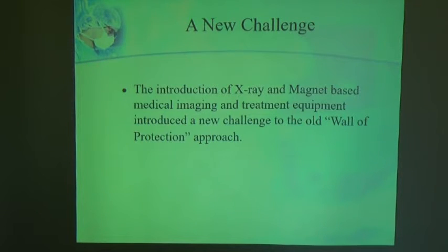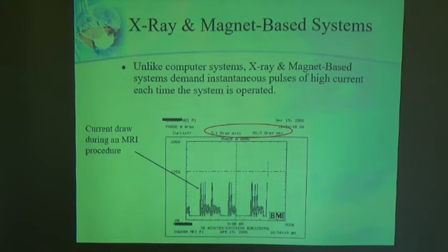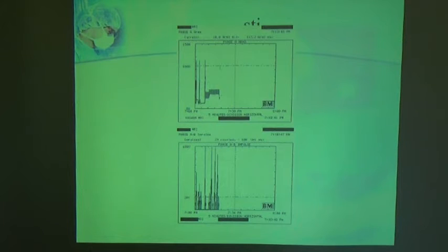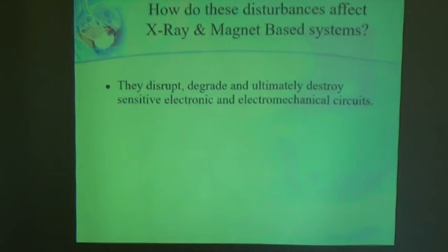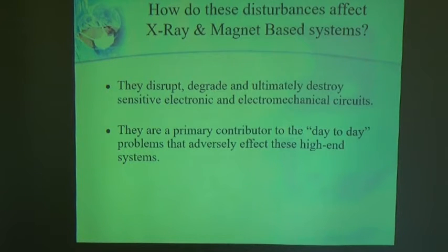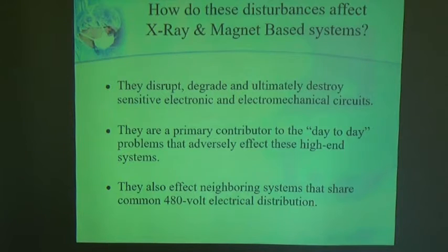The introduction of X-ray and magnet-based medical imaging and treatment equipment introduced a new challenge to the old wall of protection approach. Unlike computer systems, X-ray and magnet-based systems demand instantaneous pulses of high current each time the system is operated. The response to that demand for high current impulses is typically seen as voltage disturbances. These disturbances disrupt, degrade, and ultimately destroy sensitive electronic and electromechanical circuits. They are a primary contributor to the day-to-day problems that adversely affect these high-end systems. They also affect neighboring systems that share common 480 volt electrical distribution.